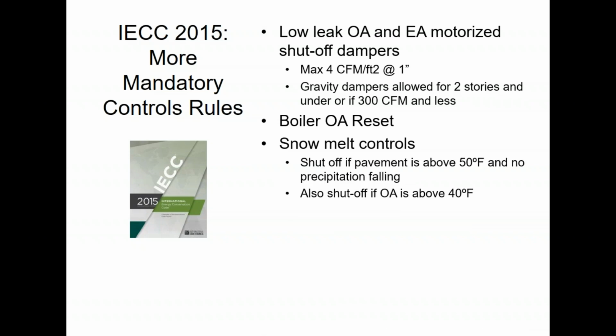If you have snow melt systems, there are 3 minimum requirements you must install from a control standpoint. You have to have a precipitation sensor, a moisture sensor, right? If there's no moisture outside, you shouldn't have a snow melt system on, right? So only if there's moisture outside. Typically, those are sensors that are mounted either in the concrete, or if you forget to do that during concrete installation, you can get one that goes out like the grass area.